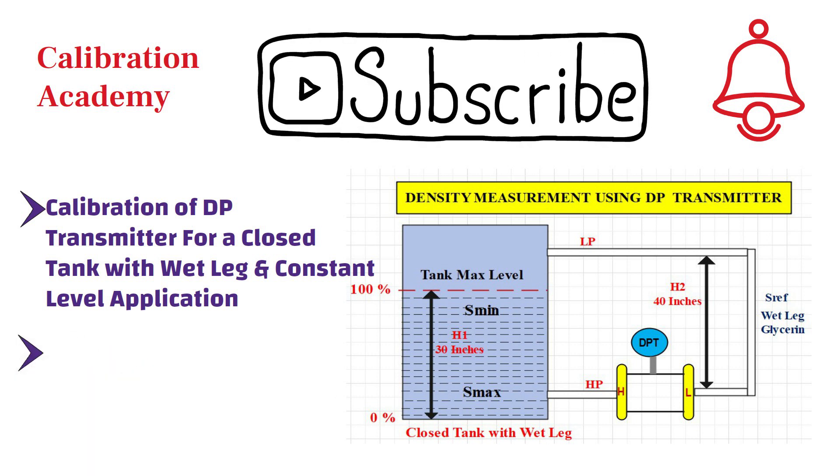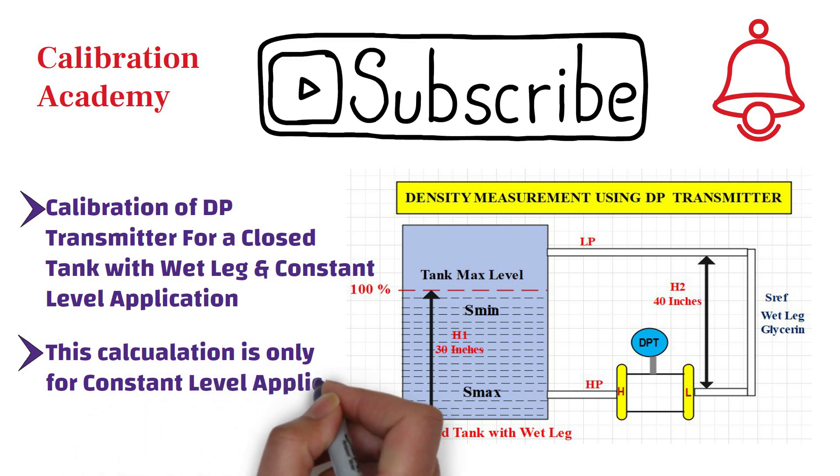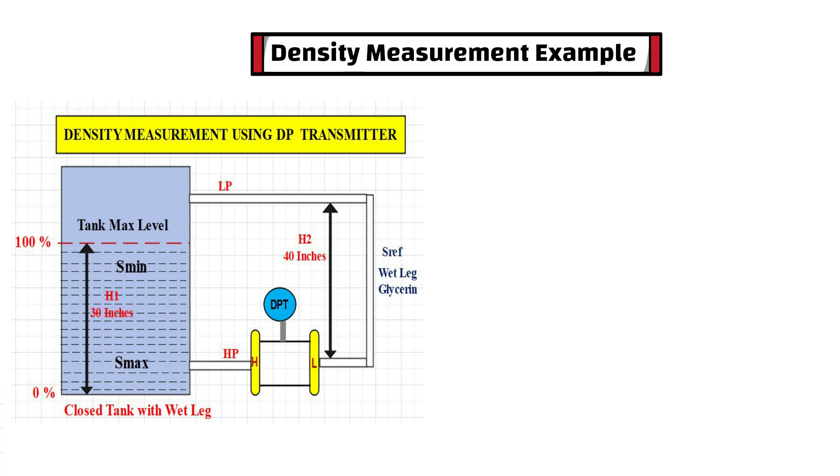It is important to note that this calculation is used only for constant level application. Now let's go to the calculation steps. As you can see, this is an example of density measurement using DP transmitter for a closed tank with wet leg.